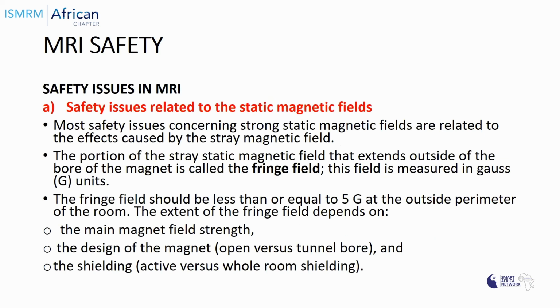Now, safety issues related to the static magnetic fields. We know that most safety issues concerning strong static magnetic fields are related to the effects caused by the stray magnetic field. The portion of the stray static magnetic field that extends outside of the bore of the magnet is called the fringe field. This field is measured in Gauss units. The fringe field should be less than or equal to 5G at the outside perimeter of the room.